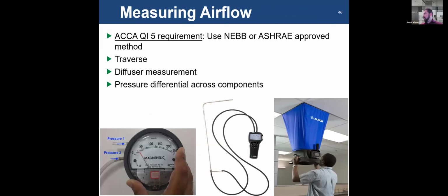So in that last slide, we talked about balancing. It's often not done in a residential setting. However, commercially, it's done all the time. This ensures that you've got the correct airflow to each of your rooms. So during your Manual J, if you did a room by room analysis, you would have figured out how much airflow you need to condition that space. You, in theory, should actually measure. I know a lot of people don't do this, and oftentimes it's not required, but you should actually be measuring how much airflow is going into that space to make sure that you are within tolerance of the airflow to that space, to make sure that space can be properly conditioned.